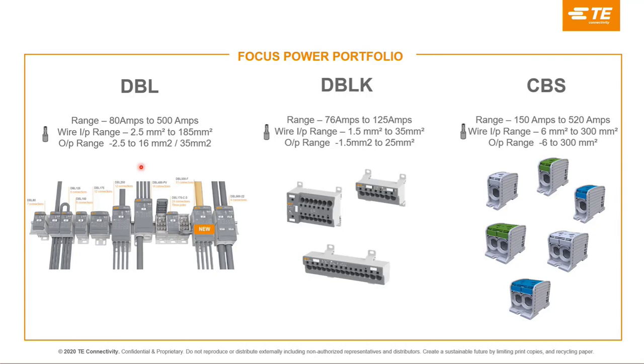Now let's switch focus to DBLK. It has similar functionality of distribution of power into secondary circuits, available in the range of 76 amps to 125 amps. DBLK is a more advanced version of DBL, and the difference lies in the type of connection employed. DBL uses screw connection, while DBLK is designed with spring-loaded technology, enabling a fast, tool-free, secure and more efficient connection system for distribution and tapping. DBLK is also the safest connection with IP20 protection, entirely covered product.